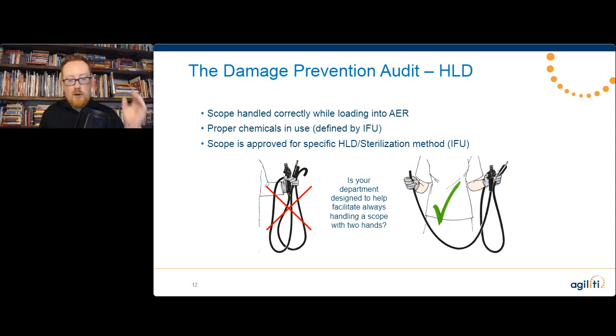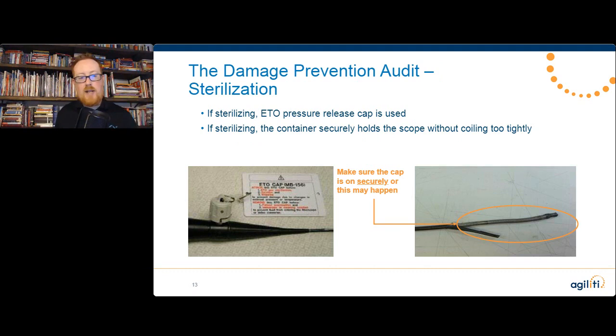All right. If we're doing sterilization, obviously we've got to make sure that the pressure cap is on, and that if we are using a rigid container for sterilization, which you probably are, that it is actually designed for a flexible scope. I have seen many instances where a small diameter flexible scope was crammed into a way too small rigid container, like the kind you might use for a video camera, and they just kind of bend it up to make it fit in there, right? And then are shocked when their devices come back damaged. It has to be designed and fit specifically for flexible scopes so that it doesn't coil them up too tightly, or else you're going to end up with lots of extra damage.